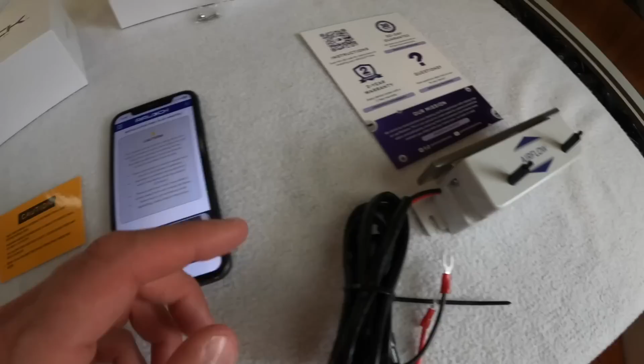Maximum ambient temperature should be less than 130 degrees; I think we're going to be okay. The ion emitters, those little whisker things right there, need to be 2 inches away from metal surfaces, and you should never touch the ion emitters while they are operating. It might shock you, apparently, so good to know.